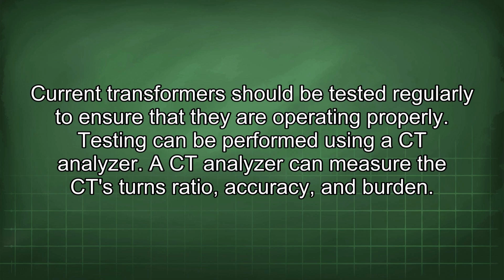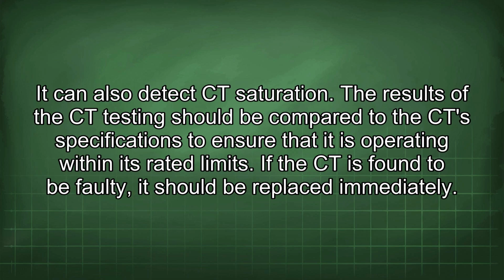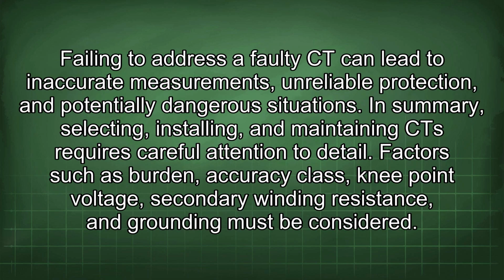Testing can be performed using a CT analyzer. A CT analyzer can measure the CT turns ratio, accuracy, and burden. It can also detect CT saturation. The results of the CT testing should be compared to the CT specifications to ensure that it is operating within its rated limits. If the CT is found to be faulty, it should be replaced immediately. Failing to address a faulty CT can lead to inaccurate measurements, unreliable protection, and potentially dangerous situations.